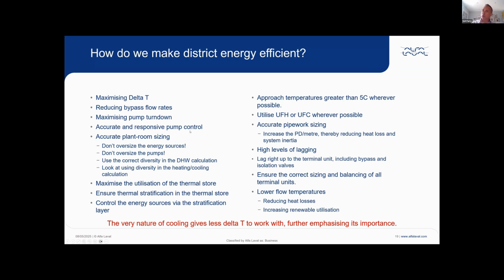And all these issues compound each other, and you end up with systems that are literally, and I've seen this, 2 or 3 times the size they should be. And the moment you do that, those systems cannot back down to the lower demand periods in a day. Maximize the utilization of the thermal store, which I'll talk about on the next slide. Ensure thermal stratification in the thermal store. I'll cover that on the next slide. And the next bullet point.